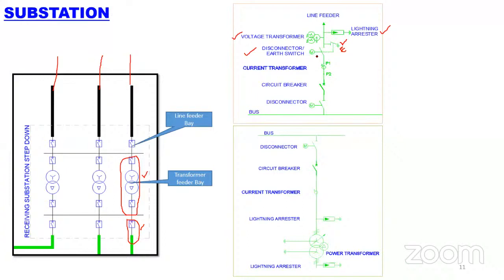Okay, the next device is the current transformer. It is a part of the instrument transformer. So there are two instrument transformers: one is the current transformer, and the other is the voltage transformer. Both are called instrument transformers, which we will study in the instrumentation subject. The current transformer helps to measure the current flowing in the incoming feeder. The voltage transformer helps to monitor the voltage. Where there is a high voltage, it will be reduced to 110 volts for monitoring purposes. Similarly, let's take a flow of 1000 amps in the high voltage network. It will give you a proportional output of less than 1 amp or 5 amps. So that is the design of the current transformer.